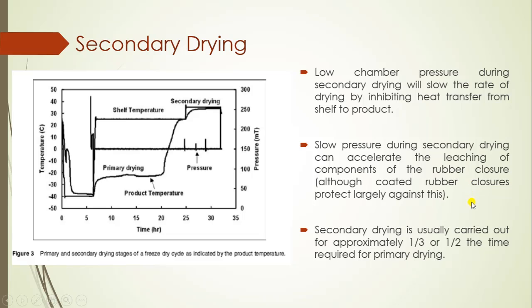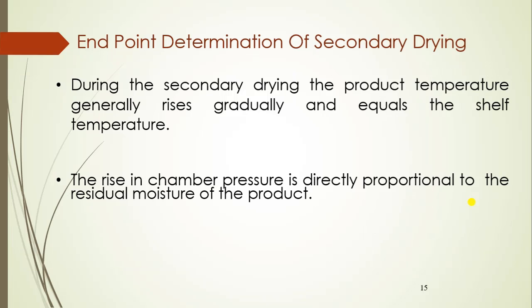Secondary drying is usually carried out for approximately one-third to half of the time required for primary drying. For endpoint determination of secondary drying, the product temperature generally rises gradually and equals the shelf temperature. The rise in chamber pressure is directly proportional to the residual moisture of the product, so an increase in chamber pressure indicates that moisture is still present in the product.